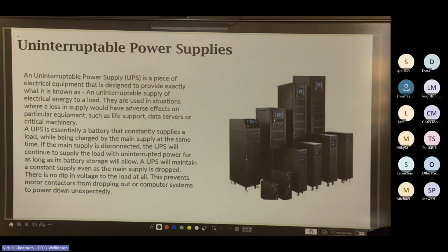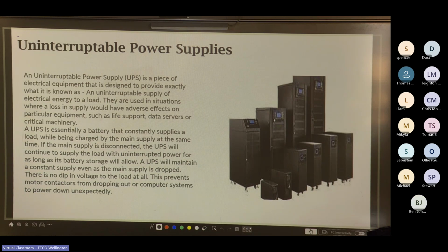So it's essentially a battery that constantly supplies a load while being charged by the main supply at the same time. So if the main supply is disconnected, the UPS will continue to supply the load until the battery runs out. So it'll maintain a constant supply even if the main supply is dropped, and there's no dip in voltage to the load at all. So it prevents motor contactors from dropping out or computer systems powering down unexpectedly, or any glitches in any special medical equipment that's hooked up to it.